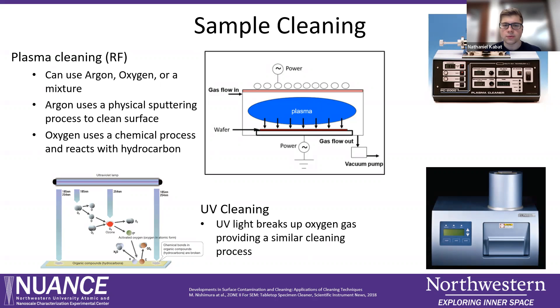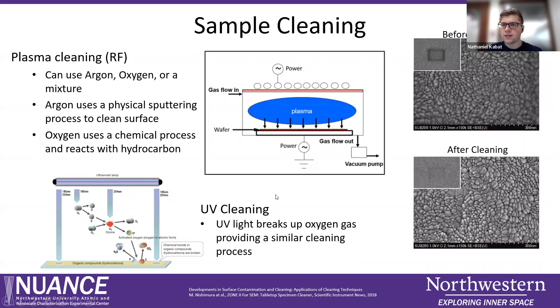The other tool you can use is UV cleaning. In a small vacuum chamber, instead of a plasma source, you have an ultraviolet light. This UV light can break down oxygen gas into molecular oxygen or ozone, and these will react with hydrocarbons on the surface of your sample and break those down, which leaves you with a cleaner sample. As an example of the benefit, here are two different images — a before and after a cleaning process. The same image I showed earlier with the carbon outline on top, and on the bottom after a few minutes of UV cleaning, you can barely see any carbon buildup on the surface. So it can be deeply beneficial if you have a sample that you're seeing this with, or if you think you have a particularly dirty sample that you want cleaned.